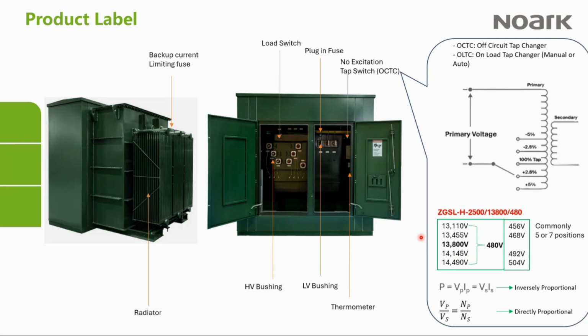So for example, when you have peak hour usage, the voltage can drop. And if the voltage drops to around 13,400, then you're not going to get 480 volts at the secondary side. You probably get 468 volts. And again, we don't want that, right? We want to have as close as possible to 480 volts on that secondary side. So when that happens, you need a tap changer. That tap changer allows you to change what you have on the primary side so that you can still get the required 480 volts on the secondary side.